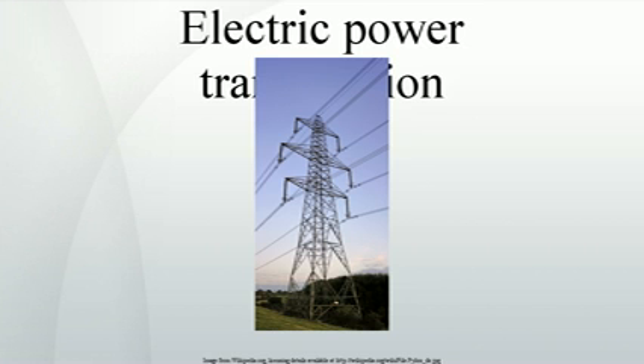A sophisticated control system is required to ensure electric generation very closely matches the demand. If the demand for power exceeds the supply, generation plant and transmission equipment can shut down, which in the worst case may lead to a major regional blackout, such as occurred in the U.S. Northeast blackout of 1965, 1977, 2003, and other regional blackouts in 1996 and 2011.